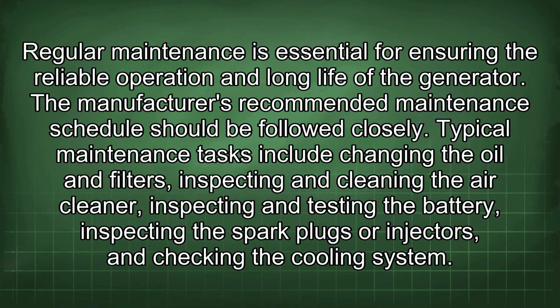Regular maintenance is essential for ensuring the reliable operation and long life of the generator. The manufacturer's recommended maintenance schedule should be followed closely. Typical maintenance tasks include changing the oil and filters, inspecting and cleaning the air cleaner, inspecting and testing the battery, inspecting the spark plugs or injectors, and checking the cooling system.